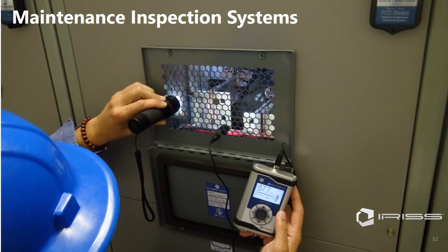So if you look at maintenance inspection systems in this image, you can see the guy is looking in there doing a visual inspection, having completed an infrared inspection, taking his ultrasound data through an embedded port. Here we also show a Delta T Alert system, which is online temperature monitoring, and an eSentry Connect system, which is the data management piece of this. All of this becomes a maintenance inspection system, basically a data collection point for the health of the asset that you're looking after.